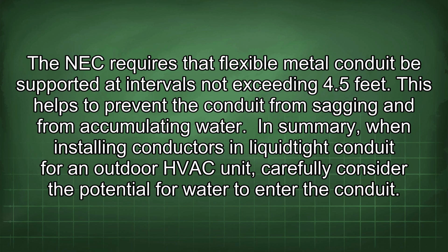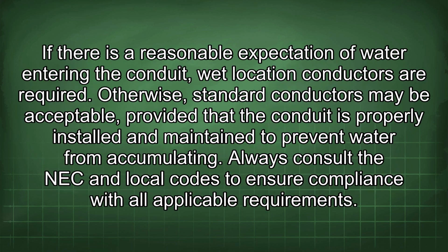In summary, when installing conductors in Liquidtight Conduit for an outdoor HVAC unit, carefully consider the potential for water to enter the conduit. If there is a reasonable expectation of water entering the conduit, wet location conductors are required. Otherwise, standard conductors may be acceptable, provided that the conduit is properly installed and maintained to prevent water from accumulating. Always consult the NEC and local codes to ensure compliance with all applicable requirements.